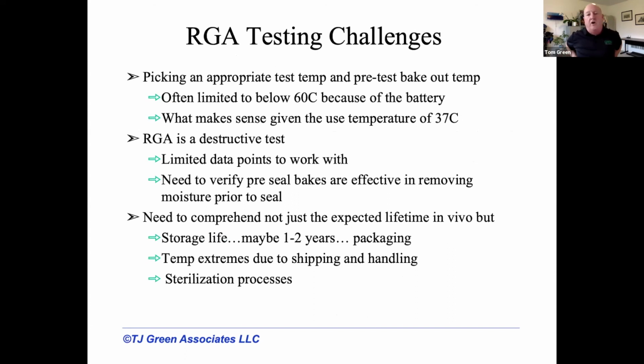So some of the challenges in the RGA test itself is that pre-bake out and test temperature. If you have a battery in there, you got to understand what that is. So maybe you dial that back and run some kind of a bake out less than the max operating temperature, and maybe test at 40 C instead of 37 to give yourself a little margin. RGA is destructive, and you really need some work up hand to verify you've got a good bake out, and you're not just worried about the expected lifetime, but the storage and shipping conditions prior to, any potential temp extremes in shipping, handling, and sterilization.